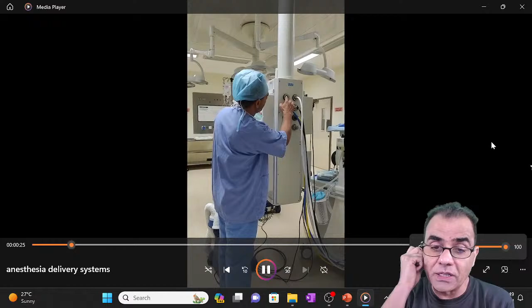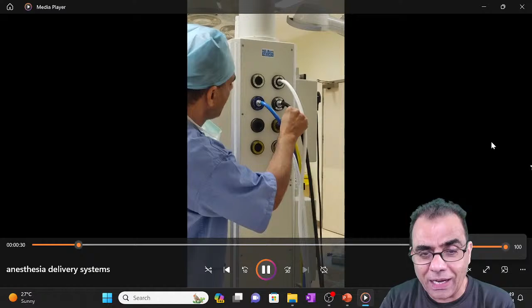So these are the gases which I'm telling. They are coming from the central supply store, and the central supply, I told you, has big storage of these gases, and from there through the central supply pipelines. And in my hospital, this may be around 200-300 meters away from the operation theater. So you can see that these pipes will be connected to this panel.